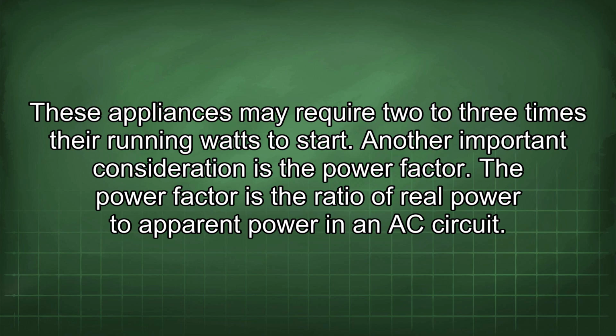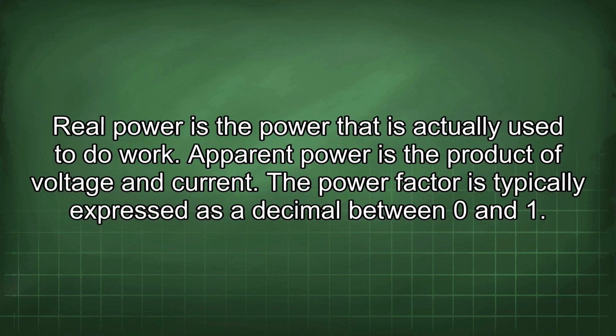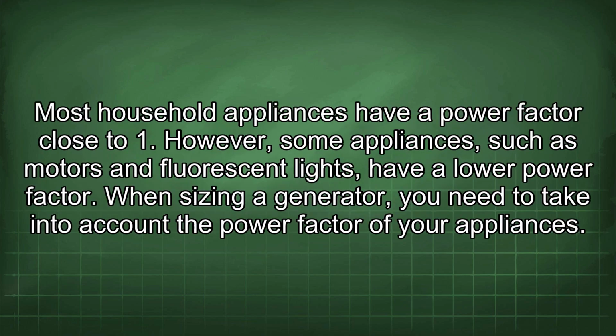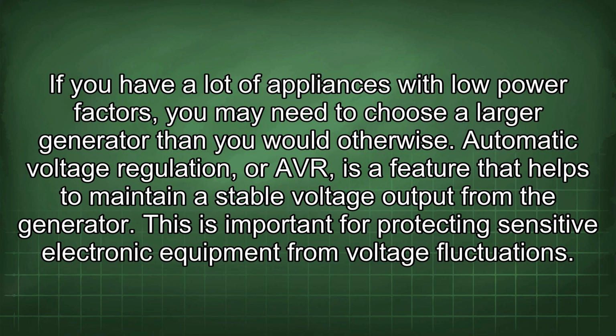Another important consideration is the power factor. The power factor is the ratio of real power to apparent power in an AC circuit. Real power is the power that is actually used to do work. Apparent power is the product of voltage and current. The power factor is typically expressed as a decimal between 0 and 1. Most household appliances have a power factor close to 1. However, some appliances, such as motors and fluorescent lights, have a lower power factor. When sizing a generator, you need to take into account the power factor of your appliances. If you have a lot of appliances with low power factors, you may need to choose a larger generator than you would otherwise.